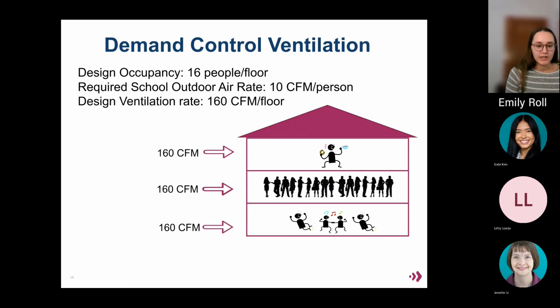As discussed, ventilation is very important for the health and comfort of building occupants. So, buildings are designed to meet specific ventilation rates. In this example, that ventilation rate is 10 CFM per person with an expected 16 people per floor. In a building with no demand control ventilation, you would see 160 CFM delivered to each floor. However, as seen here, a typical building is not always at its design occupancy. Some floors might have 16 people, but others will have less.